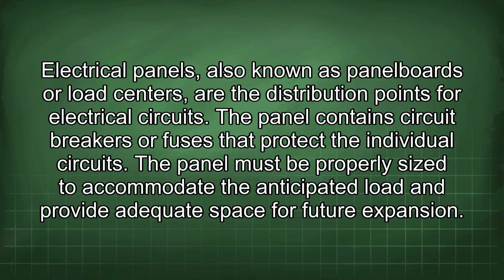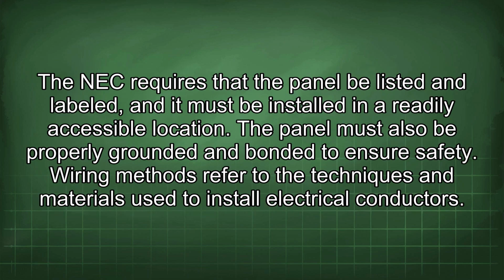The panel contains circuit breakers or fuses that protect the individual circuits. The panel must be properly sized to accommodate the anticipated load and provide adequate space for future expansion. The NEC requires that the panel be listed and labeled, and it must be installed in a readily accessible location. The panel must also be properly grounded and bonded to ensure safety.